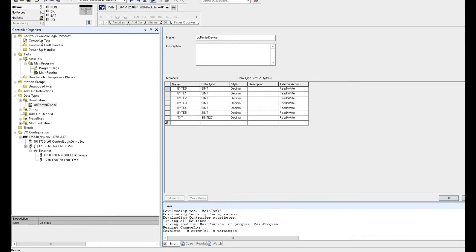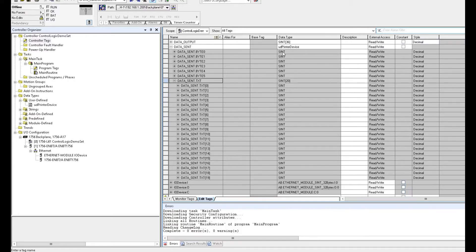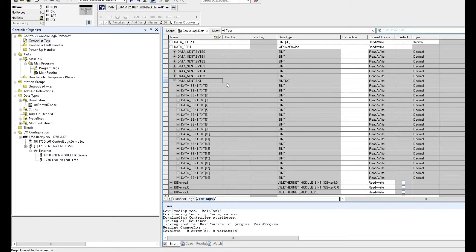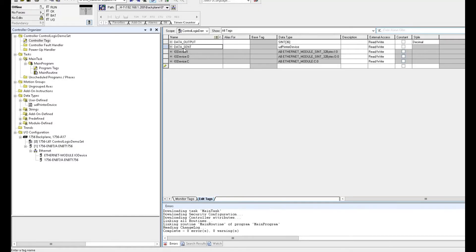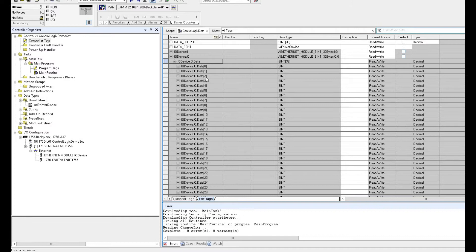Based on this UDT, I go to the controller tag and create 'data_sent'. I create this tag name based on this UDT data type structure. After creating data_sent, the structure is the same as the manual requires — from zero to five, the top six bytes are a byte type, and the following is text. Usually we will use a COP command to copy this tag to the output — copy data_sent to the Ethernet IP device tag name: iodevice.output.data.